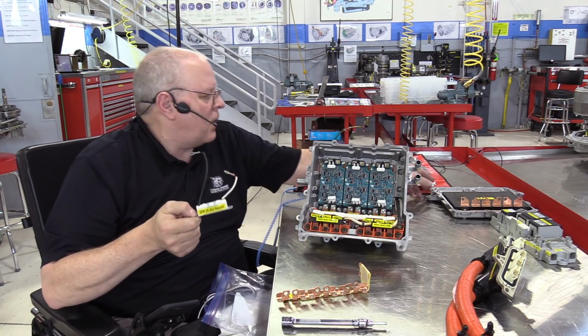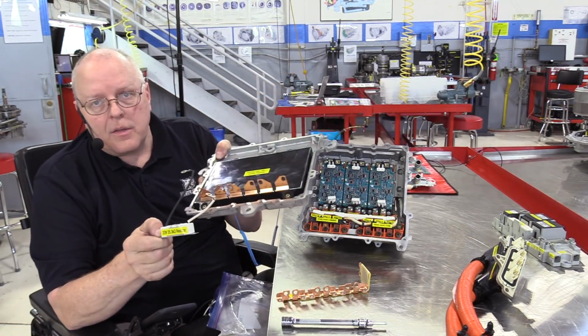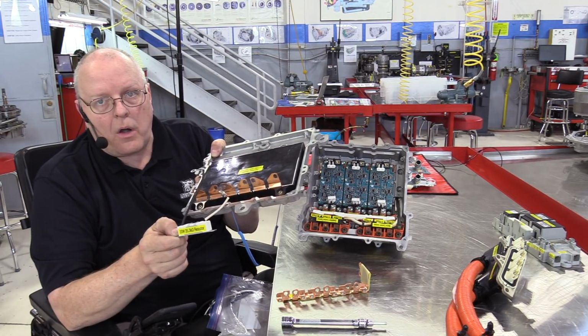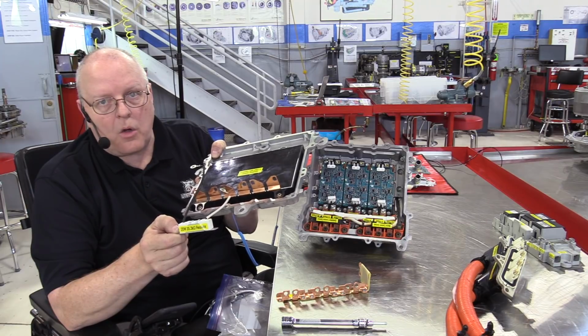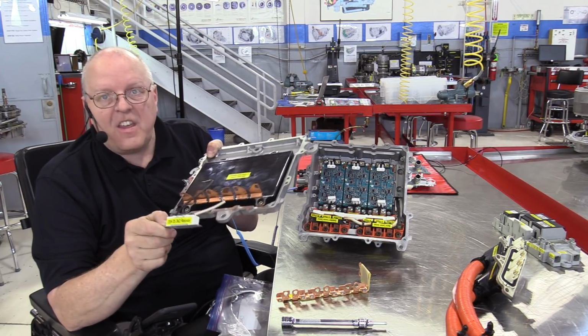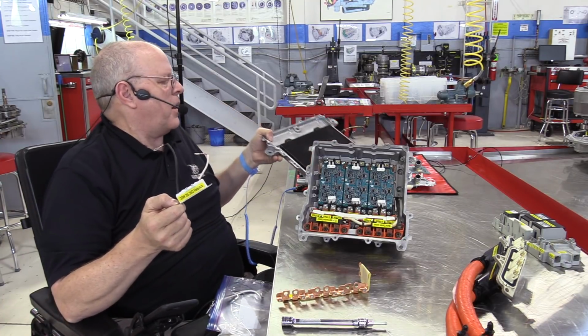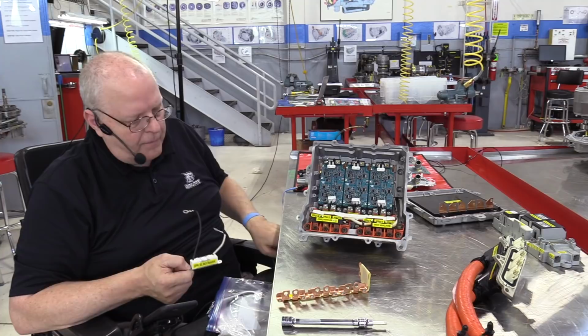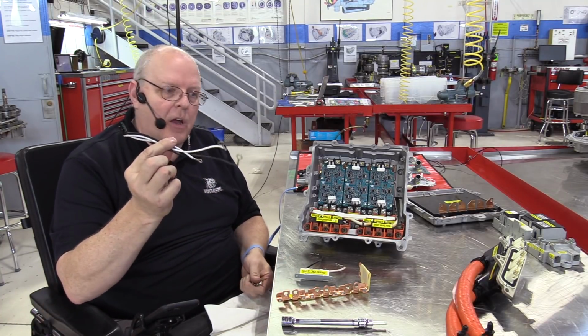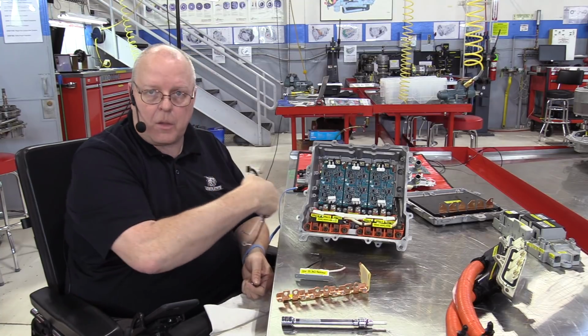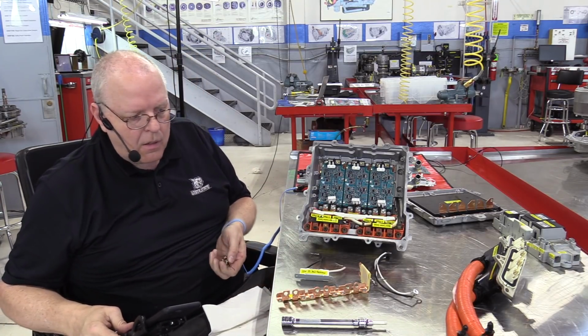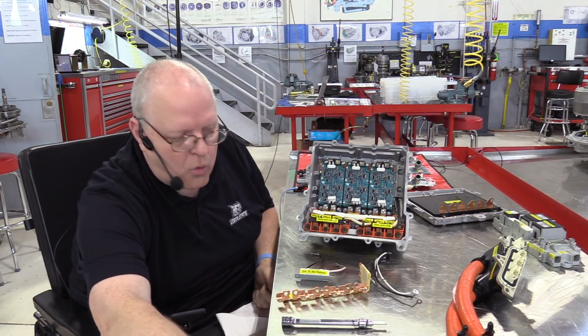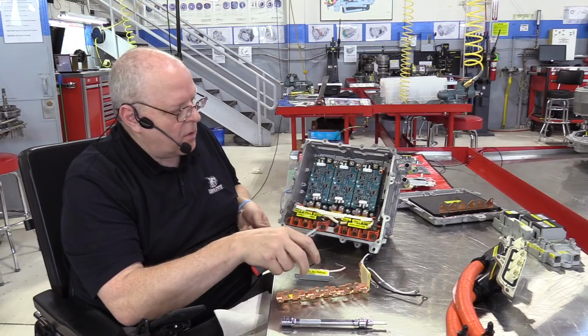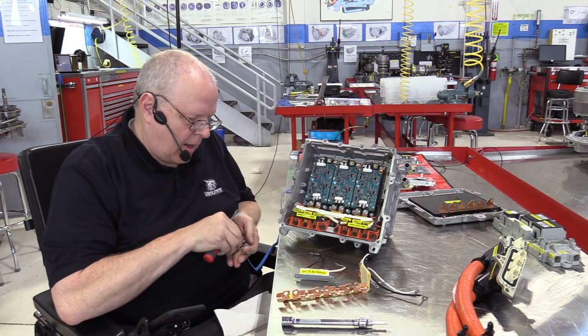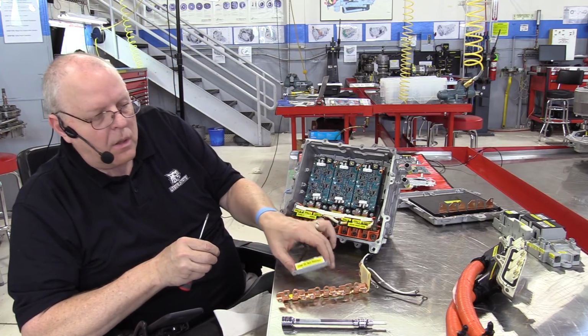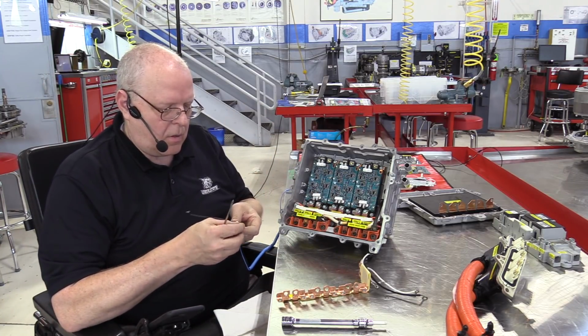This resistor's job is to discharge the smoothing capacitor every time you turn off the power to your car and the contactors in the high voltage junction block open. This is what discharges these 3 capacitors. They're all wired in parallel with each other electrically. And then we have some voltage feed lines from the DC high voltage that goes up to the upper case to feed some of the modules that are in control of the TCM. So the first thing we'll do is put in our high power, high wattage resistor here.